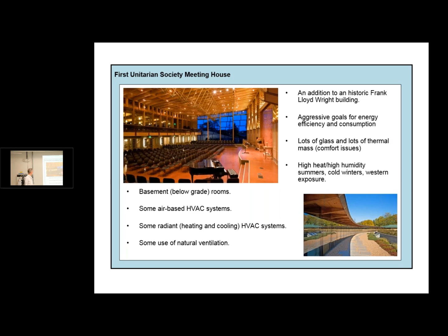This is a diagram just to show you how unconventional this system was. The main center point of this was a very large water source heat pump, which ended up being a ground loop. You've got this main heat pump, which is either providing hot water in the wintertime or cold water in the summertime, and it's feeding hot water coils in three different air handlers and in an energy recovery ventilator, and it's also running a bunch of radiant floors. It's a very unconventional system.